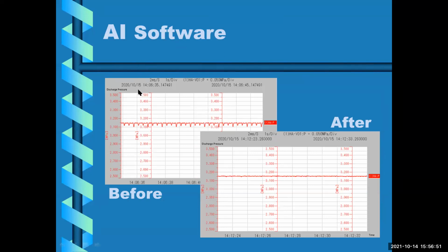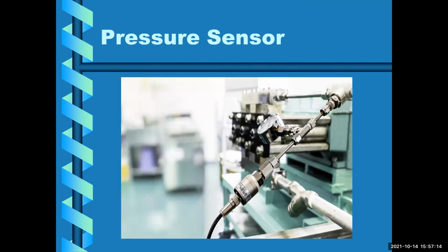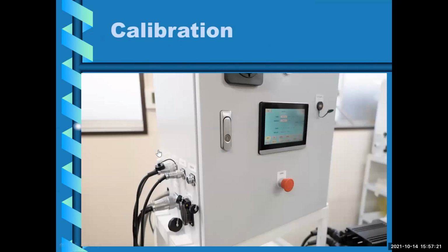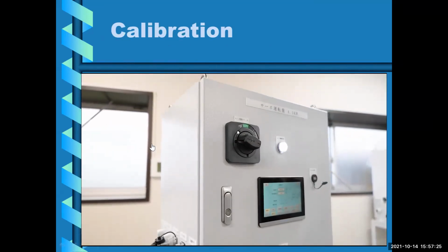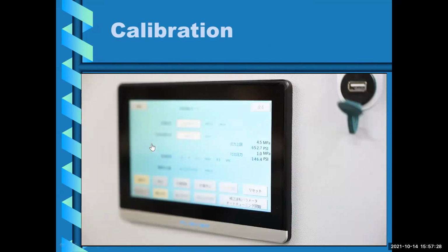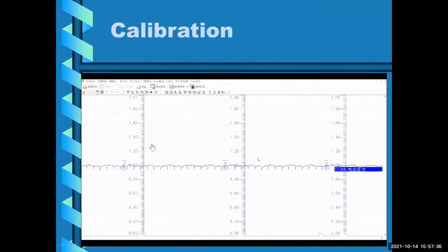In addition to modifying the pump design for high accuracy and lower pulsation, our engineers have developed AI software to finely adjust the motor speed to minimize pulsation. Trace plots show the difference between before and after activating the software. A pressure sensor is placed on the distal side of the pump to measure and send pressure data to the controller. The control system developed by Fuji Techno captured the pressure values. As you will see, the fluctuation of pressure has a certain pattern of highs and lows. The software learns the pattern and adjusts the motor speed to calibrate output and minimize pulsation.